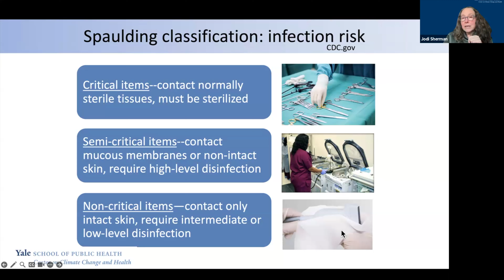So what's now happened is someone in their infinite wisdom said, well, we're really unsure about the handle because it touches the tongue blade. We know the tongue blade is semi-critical, and historically goes down to central sterilization and supply for decontamination. The handle just touches your hand. So therefore, historically, it was cleaned at point of use, low level, low risk cleaning. Someone in their infinite wisdom said, oh, but they're touching each other. They're touching each other, and therefore the handle should also be considered intermediate risk.